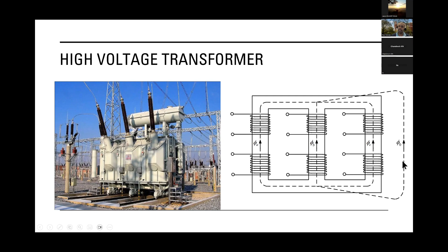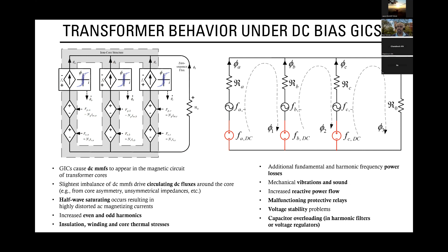this is what we call a magnetic circuit. It represents the flux, the magnetic field that flows in the core. And you can see that there's now an anomalous DC component. This GIC is creating a DC magnetic field when the core is normally supposed to have an alternating magnetic field. And that causes the transformer to draw a very distorted current. So the GIC that flows through the transformer distorts the magnetic field, and it causes the transformer to draw what we call a non-sinusoidal current. I'll show you in the next slide what that current looks like. But it causes overheating, harmonic distortion, vibration, audible sounds, and malfunctions.